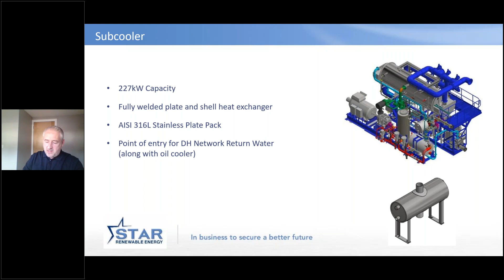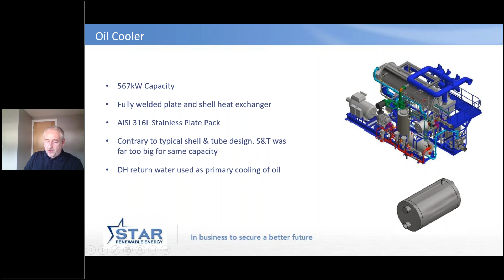And we're able to get the heat out of the oil cooler at above the condensing temperature, because the oil going into the oil cooler is around about 100 degrees. And that's really quite a rich grade of heat. So we're always trying to get stuff at the highest possible temperature that we can.